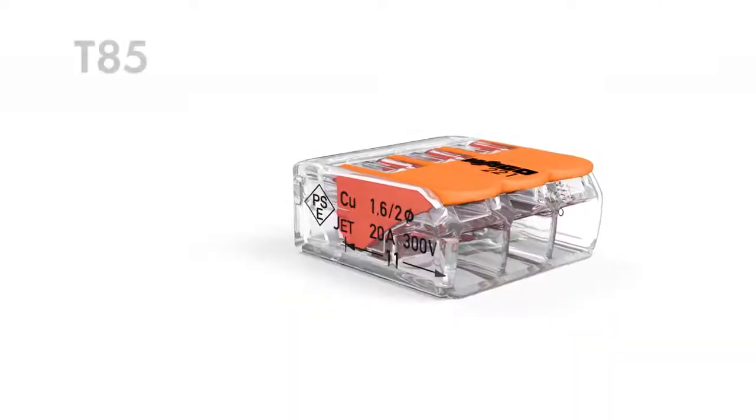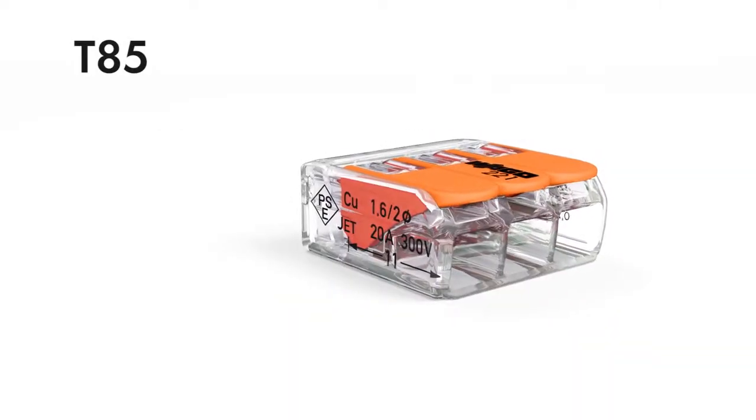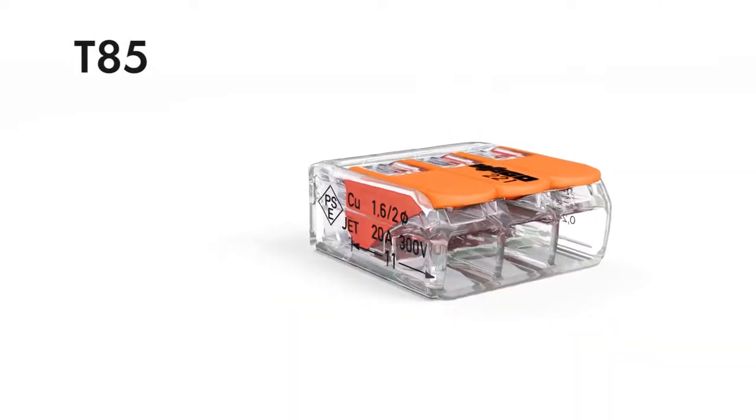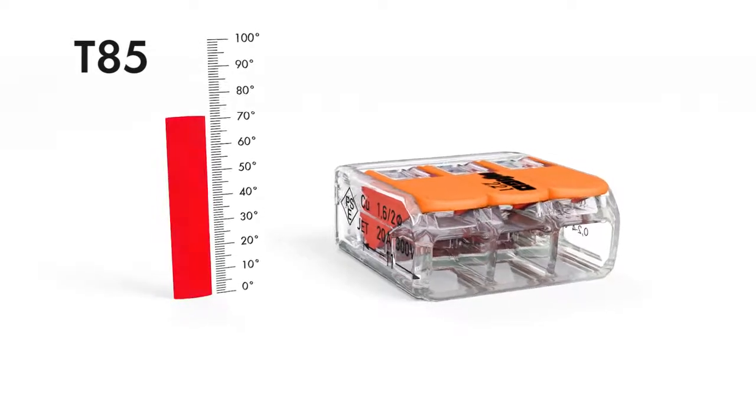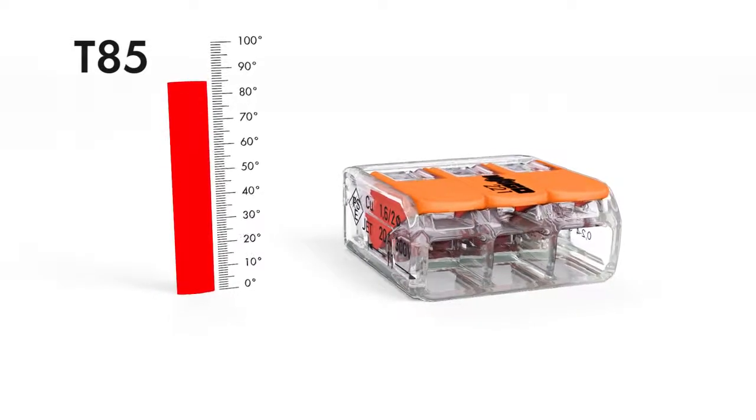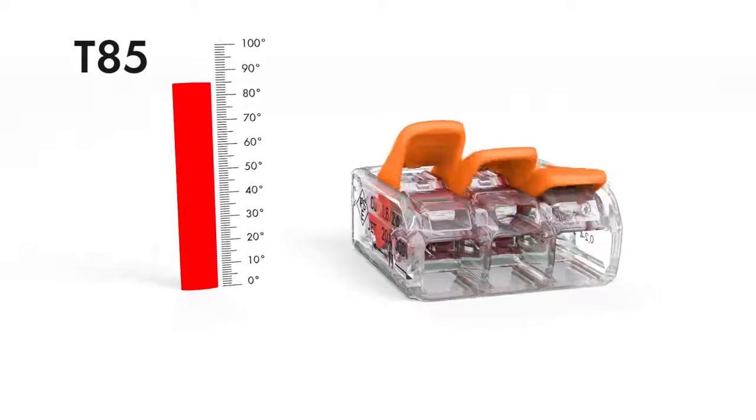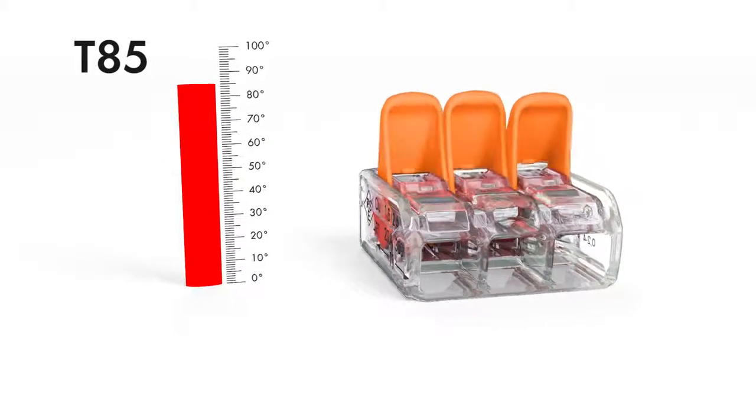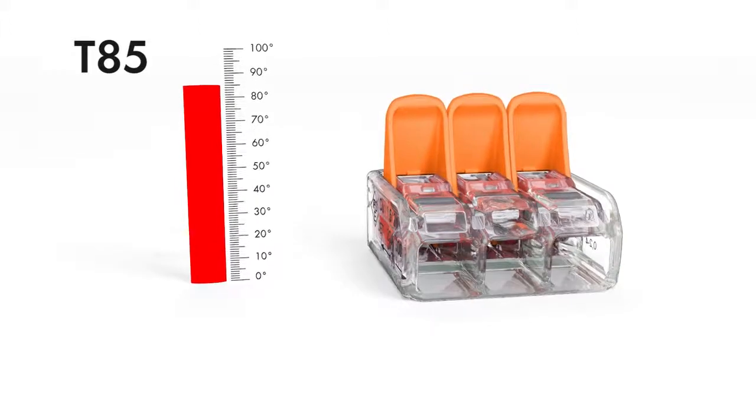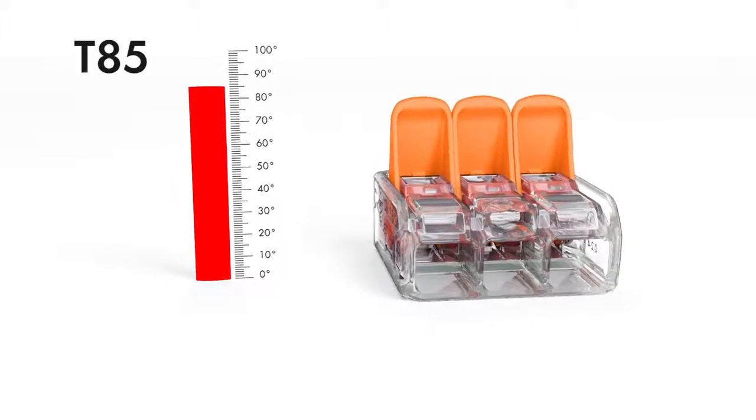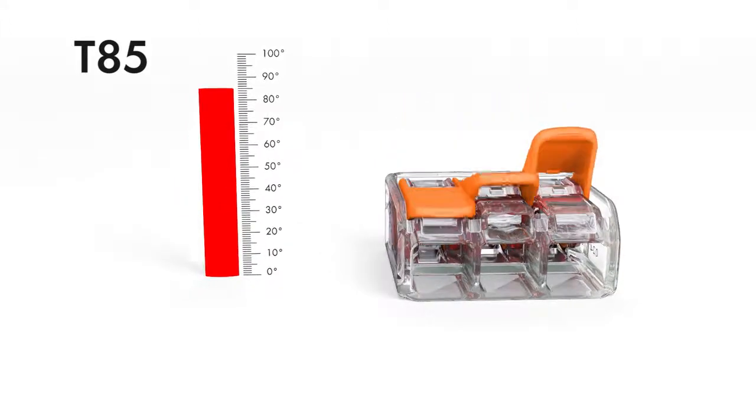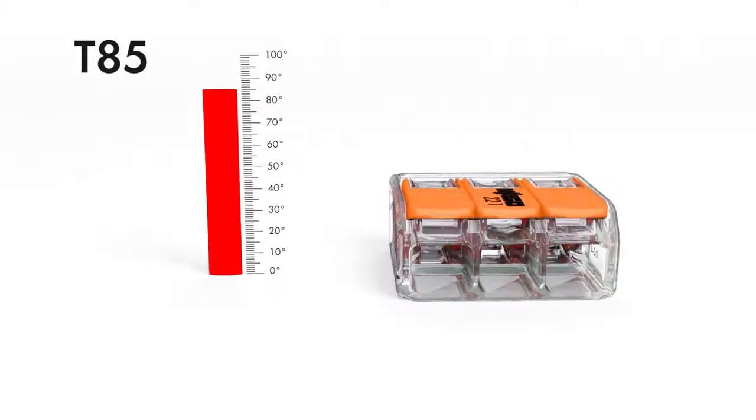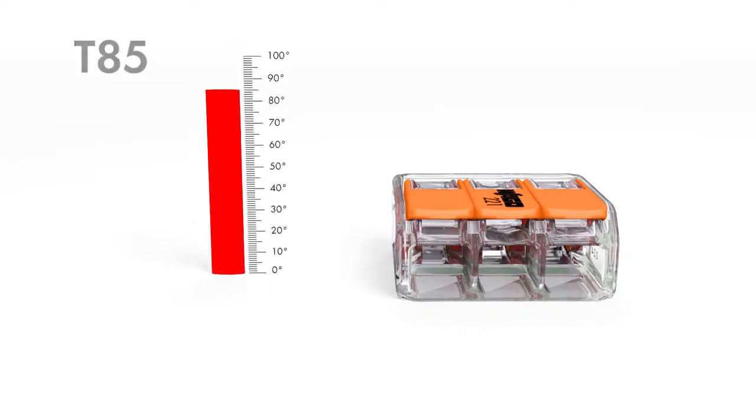The 221 series is rated to T85 in compliance with EN 60998, making it perfectly suited for increased ambient temperatures up to 85 degrees Celsius. Take advantage of economical installation benefits.